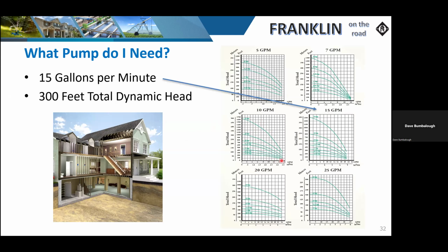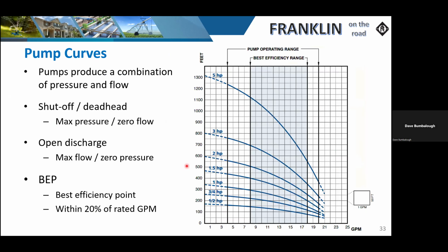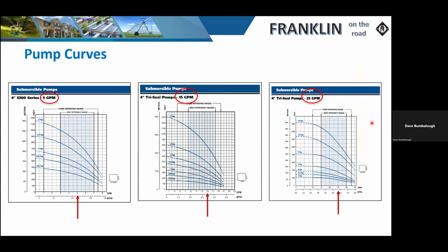It's pushing it kind of towards the right side of the curve. I could definitely do the 20. It's going to be pushing back towards the left-hand side of the curve. So I've got basically 3 pumps that I can use here to achieve my goals. So if I do have the option for the 15, I'm going to grab it. And I'm going to take a look at it and make sure that I'm somewhere in the best efficiency range. And that's ultimately where you want to strive to be.